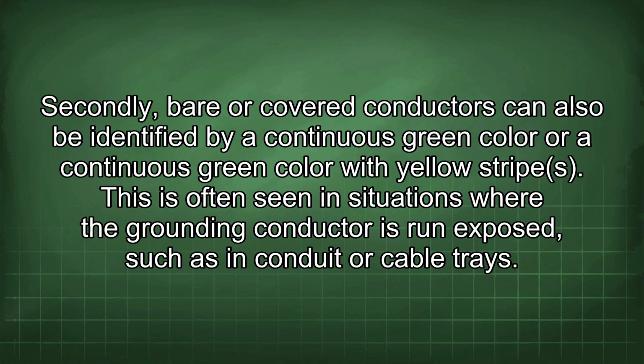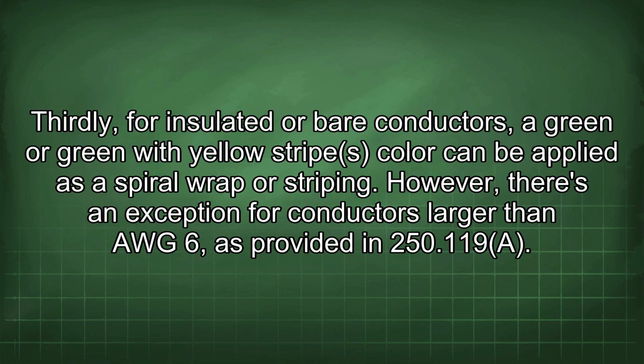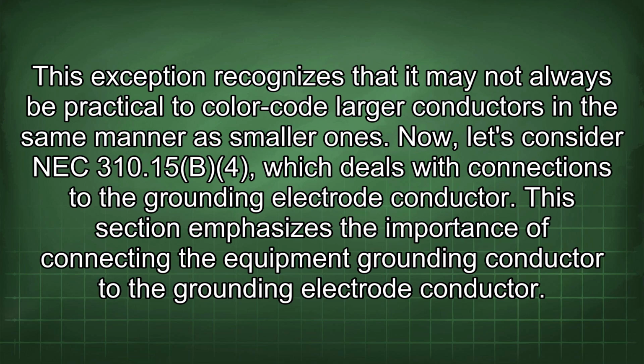Secondly, bare or covered conductors can also be identified by a continuous green color or a continuous green color with yellow stripes. This is often seen in situations where the grounding conductor is run exposed, such as in conduit or cable trays. Thirdly, for insulated or bare conductors, a green or green with yellow striped color can be applied as a spiral wrap or striping. However, there's an exception for conductors larger than AWG 6 as provided in 250.119(A). This exception recognizes that it may not always be practical to color code larger conductors in the same manner as smaller ones.